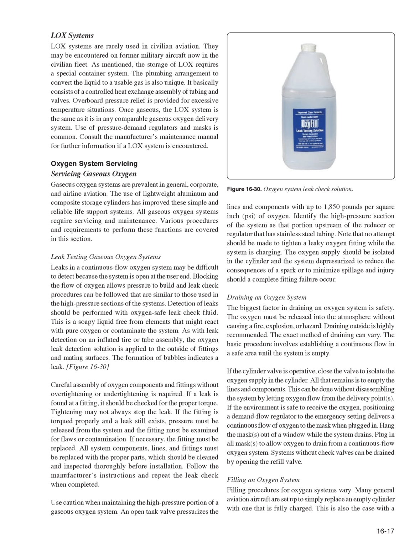All gaseous oxygen systems require servicing and maintenance. Various procedures and requirements to perform these functions are covered in this section. Leak testing gaseous oxygen systems. Leaks in a continuous flow oxygen system may be difficult to detect because the system is open at the user end. Blocking the flow of oxygen allows pressure to build, and leak check procedures can be followed that are similar to those used in the high-pressure sections of the systems.